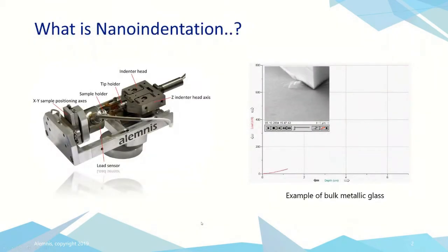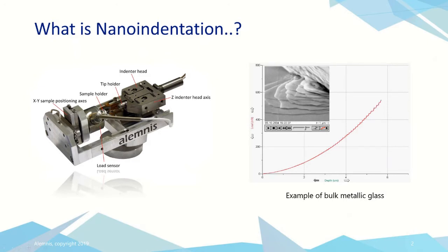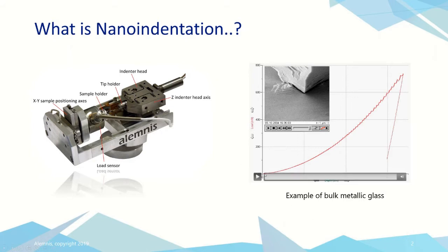Here we can see a basic Alemnis system, and we can see an example of a typical nanoindentation. When we're indenting, we're using an indenter of known geometry, and we're indenting the sample either under load control or under displacement control. Now the system works using an actuator here on the right where the indenter is placed, and the sample is mounted on an SEM stub here on the load cell. It's a little bit different when we optimize this system into the NenoVision LiteScope, which you'll see in a little while. Now, the resultant test, we basically generate a load displacement curve.